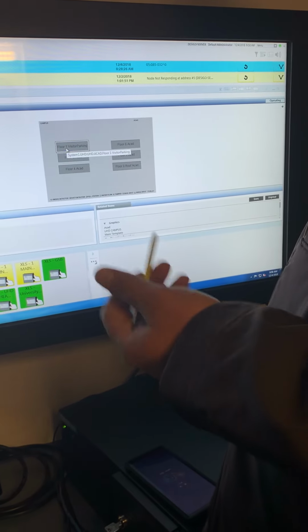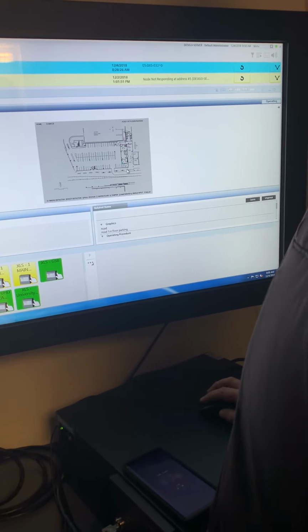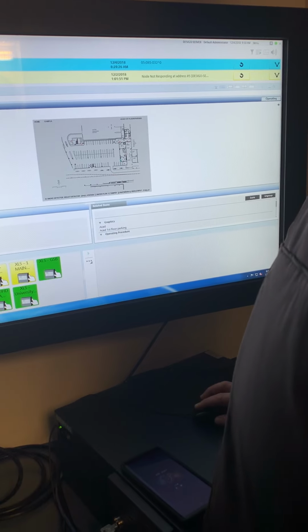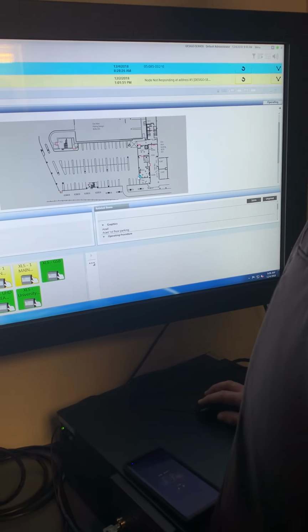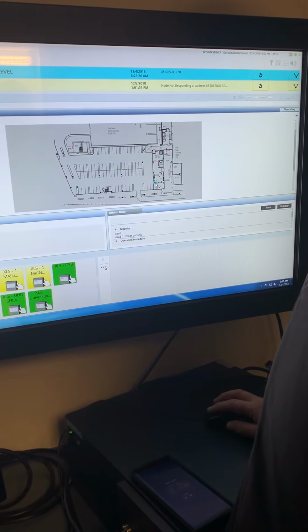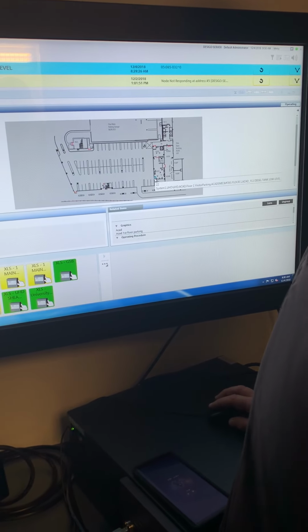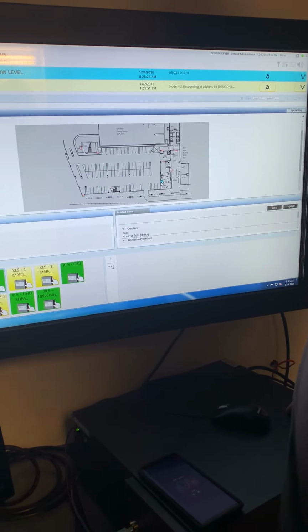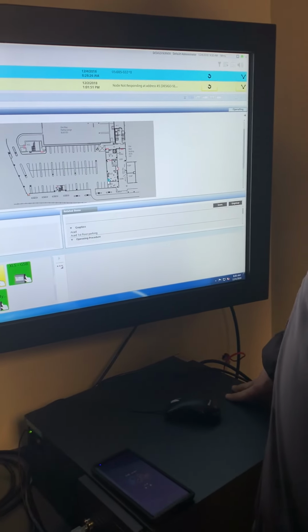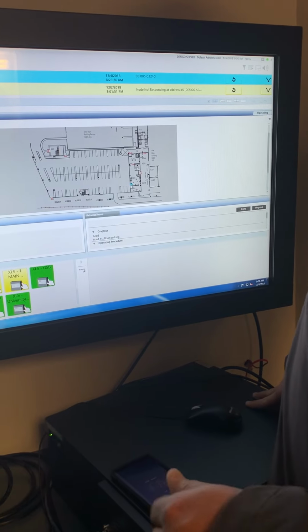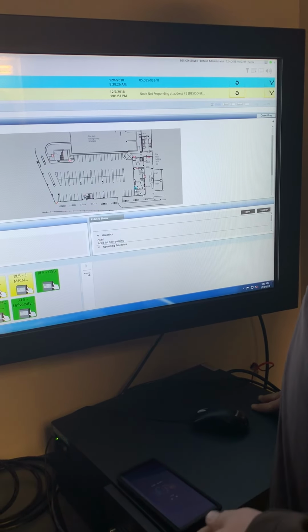So if I go to ACAD, double click on ACAD, it shows my first floor visual parking is where my supervisory is at, because that's blinking blue. And see, you can zoom in a little bit and see how those devices are blue. Those are the ones that are in supervisory. So what does that supervisory mean? A supervisory is like a tamper switch. Your fire pump run, fail, phase reversal, and out here the duct detectors are also programmed to supervisory.